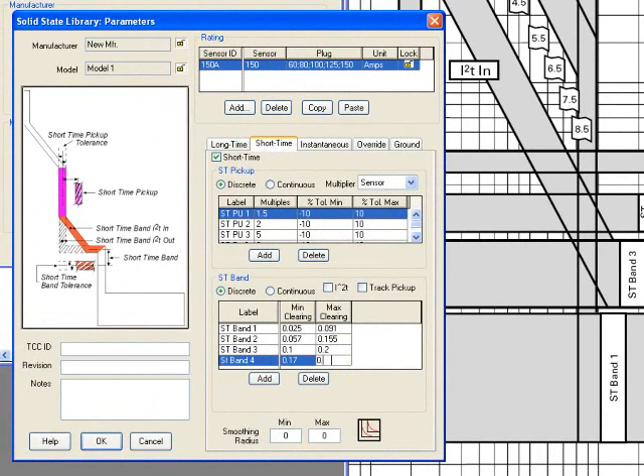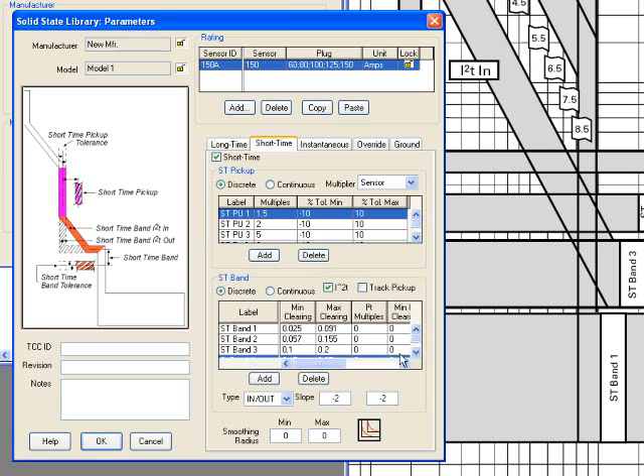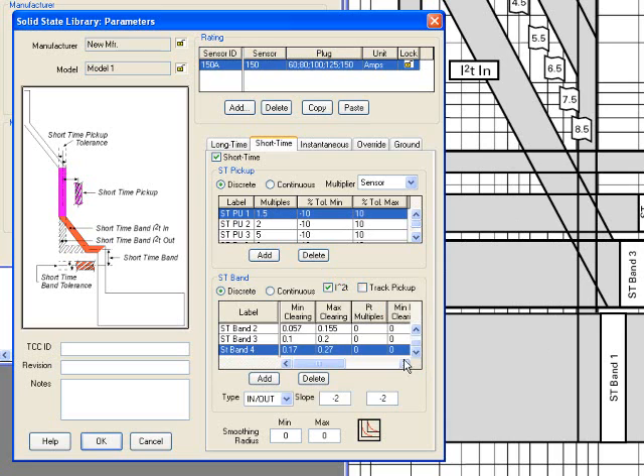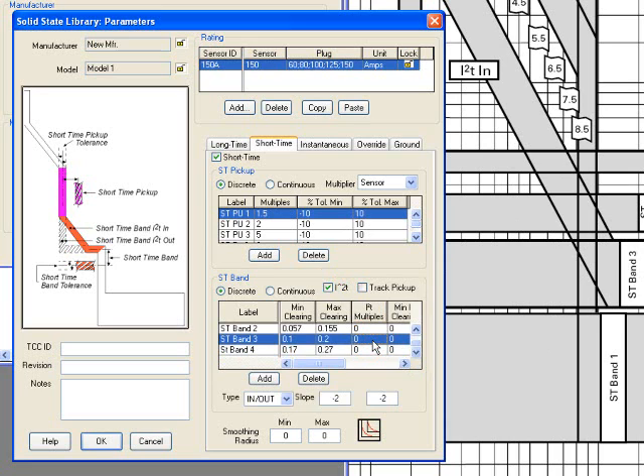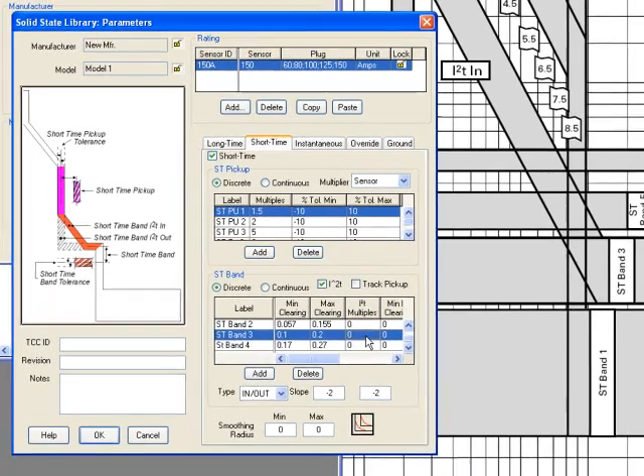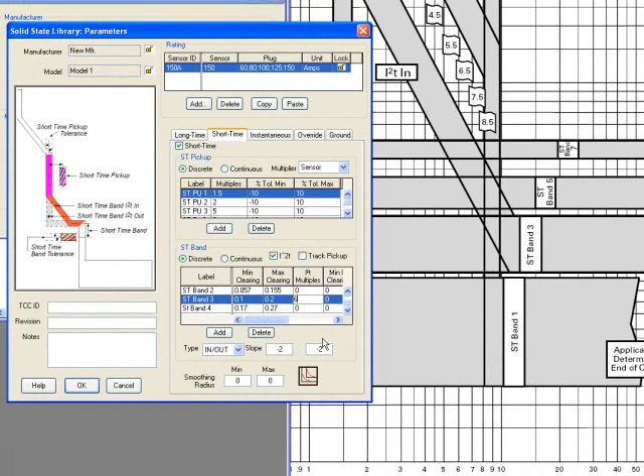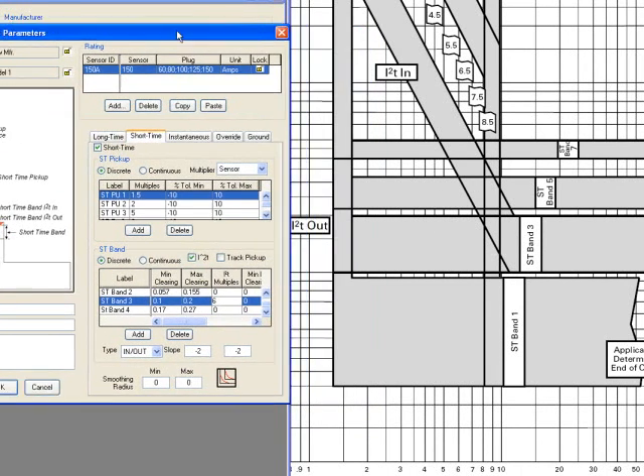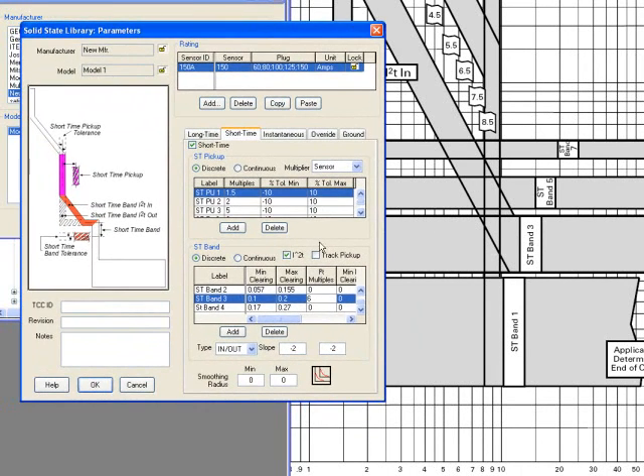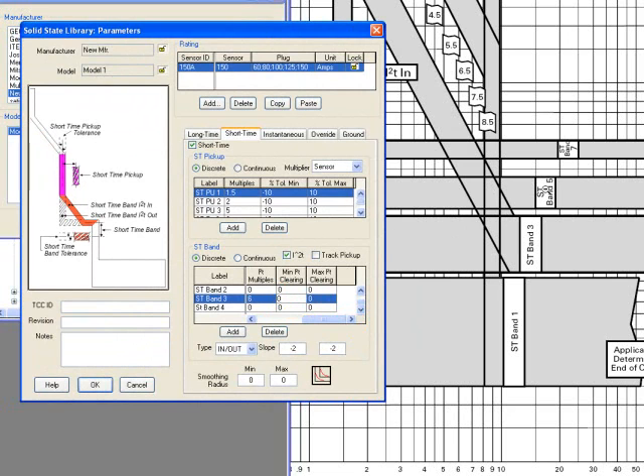As you can see, the Short Time band, if you check this box, there are new fields that are added to your list, and you have to specify the Short Time band. You'll need to specify the Short Time band multiplier. For example, in this case, the Short Time band goes with a 6 times multiplier, and you have to select the minimum clearing and the maximum clearing times with respect to that 6 multiple.